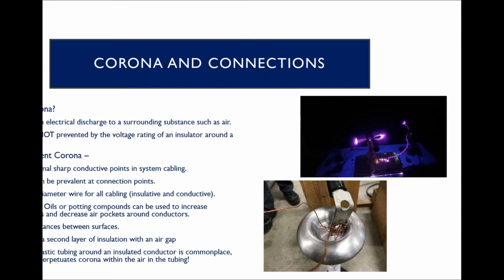So really what happens is it will extend out and it will energize or ionize the air around your conductors or around your connections. It typically comes from sharp points, as the voltage at sharp points will have an easier path into the air. So one of the things to note is that corona is not prevented wholly by the insulative level of your wire. So if you have a wire with an insulation rating of 100,000 volts, for example, that doesn't mean that it will not generate any corona. It also doesn't mean that it will necessarily be completely safe around that.